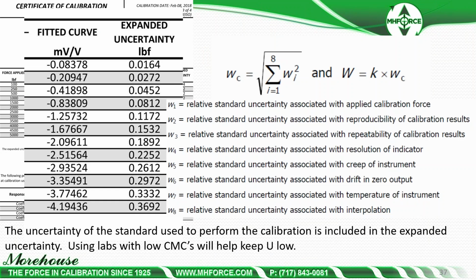And if we start looking at expanded uncertainty, this is the 5,000 pound cell we did, the points, millivolt values, and you can see the expanded uncertainty of this cell ranges at that 100 pound 2% first test point at 0.0164 to, at capacity, 0.369. So if we're calculating expanded uncertainty in accordance with the ISO 376 standard, there are 8 things that we must consider per the standard. There are additional things to consider, certainly, but there are 8 that are built into it.